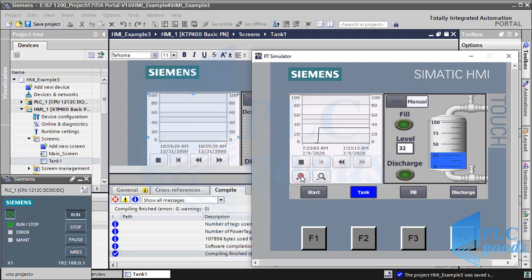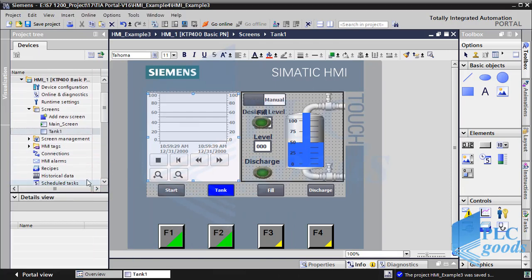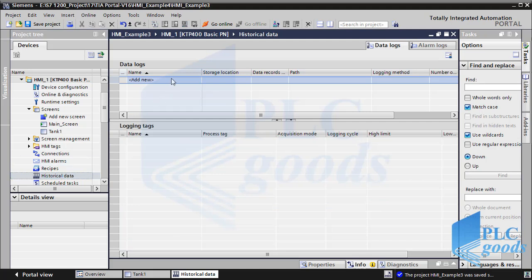Now, instead of the previous table, I can magnify the trend view or stop that. Let's see how we can store an industrial process parameter, like the liquid level, on our computer or on external memory. From the left window, select historical data. Let's specify a name for the new data log. Then we can change its settings like the output format, the number of data records to be logged in each data log, the paths where the log entries are saved, or check this box to start data logging automatically.